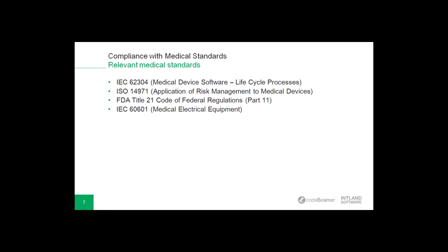And the next one is the ISO 14971, which lays out the process for identifying, evaluating, and reducing or mitigating the risks associated with medical devices. It also contains parts about monitoring the effectiveness of the risk control measures. The standard applies also to all stages of the development lifecycle, requiring developers to specify, execute, and report on the risk control processes throughout the lifecycle.